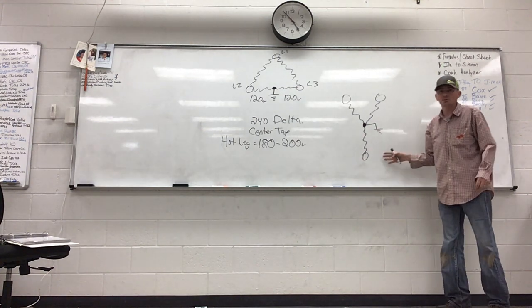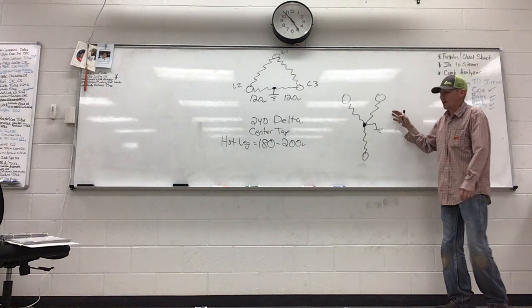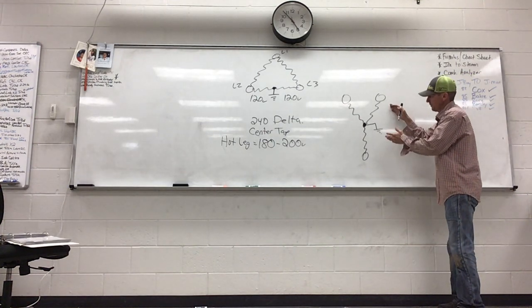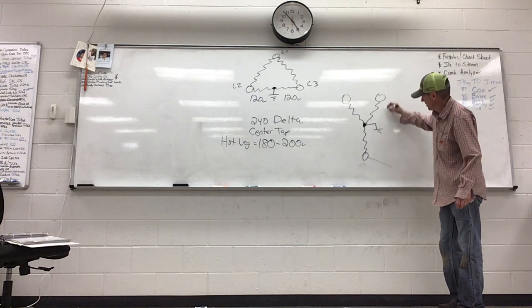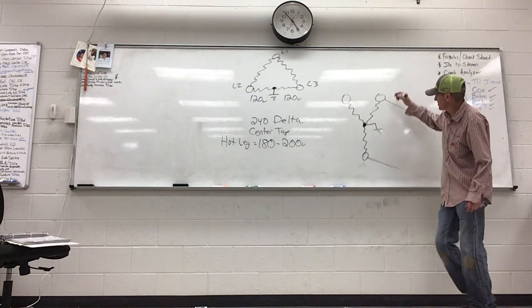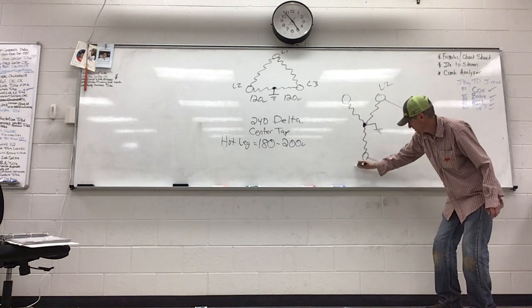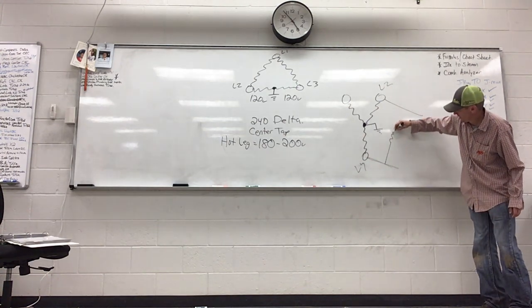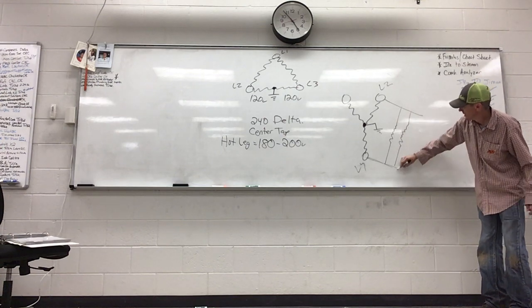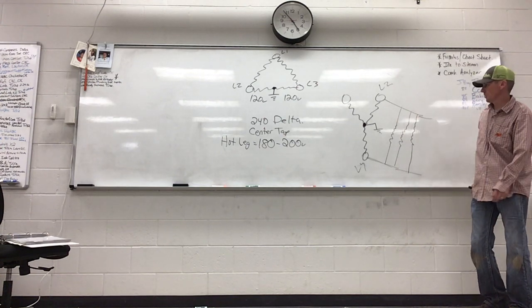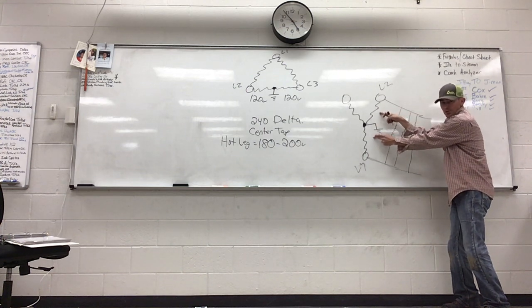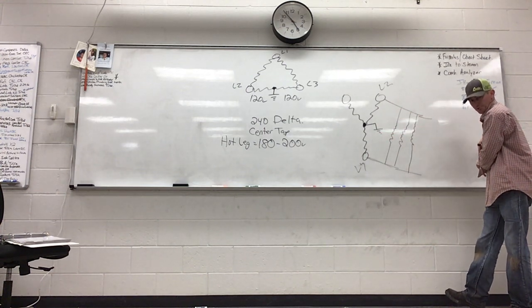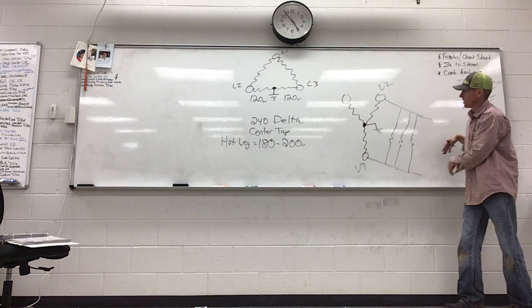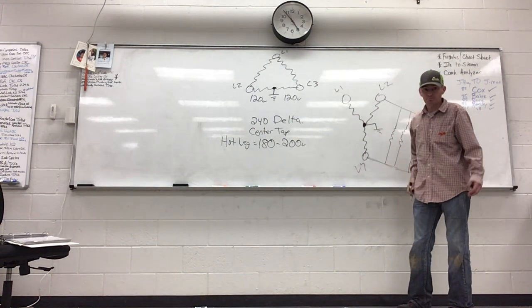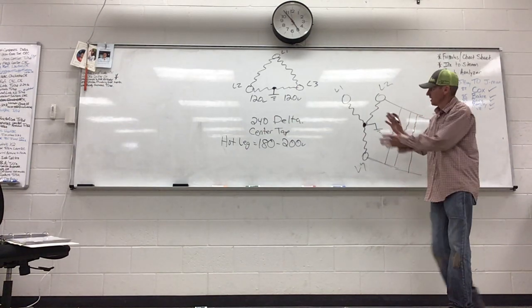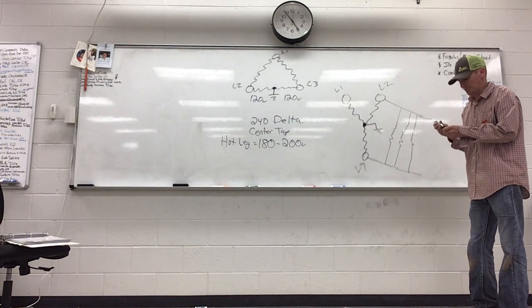You need to keep this transformer balanced, okay, because of what we're going to lead into. Let's say they got a bunch of single phase package units on the roof, and they put them all between, let's say this is L2 and this is L3, and they've got a gazillion rooftop units between 3 and 2. Well guess what, 2 and 3 are sitting here doing all this work, running all these rooftop units, all these single phase units. L1 is just sitting back here like, this is a joke, I ain't doing nothing.